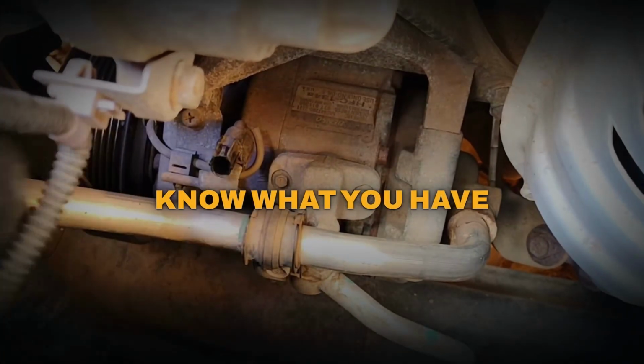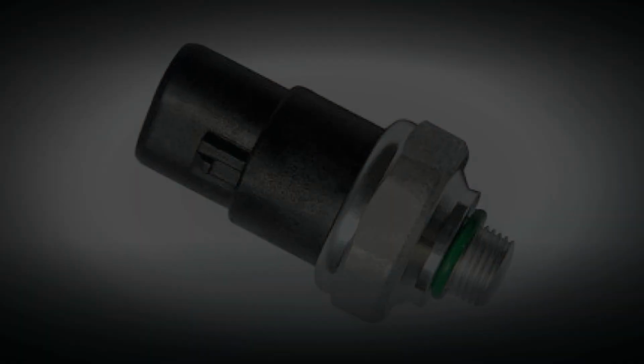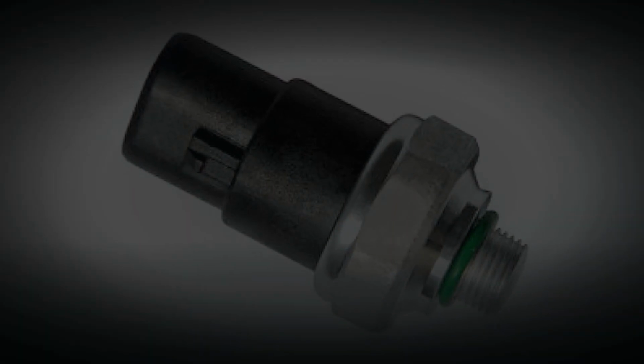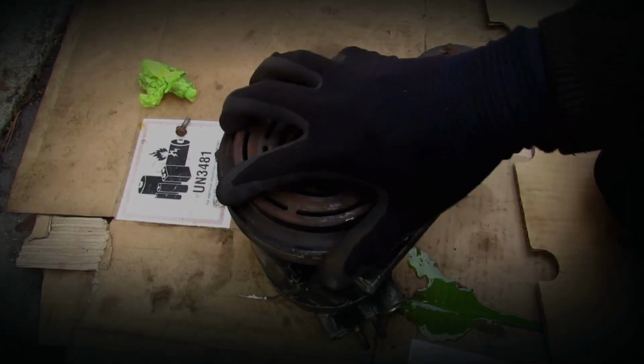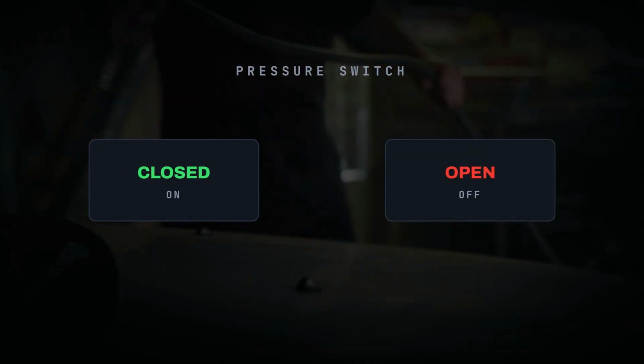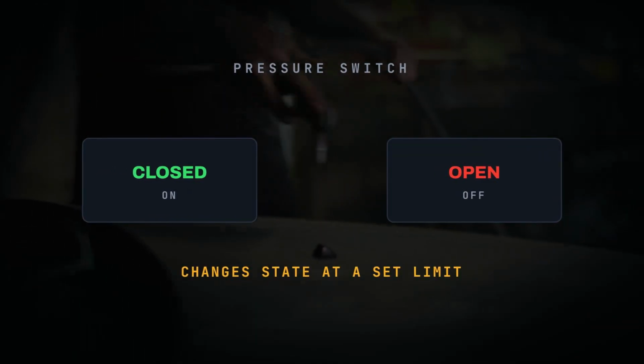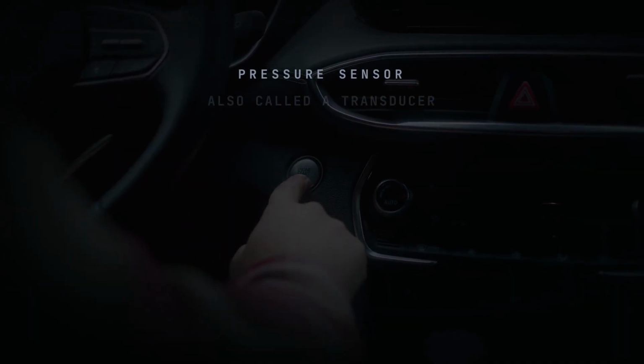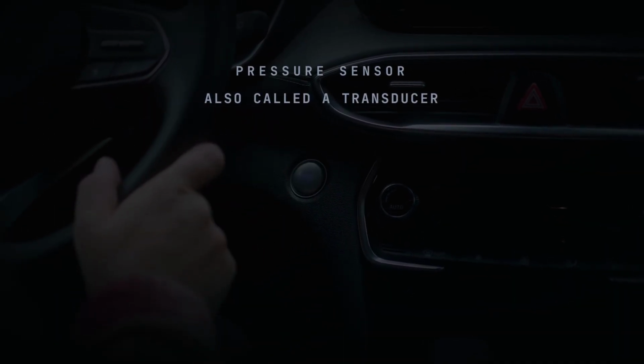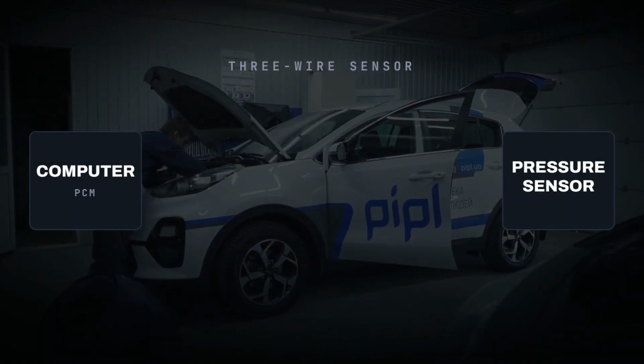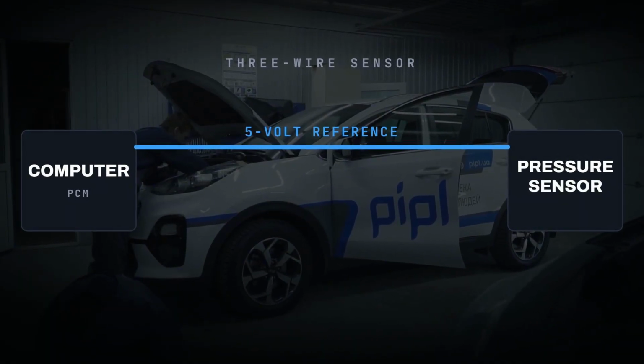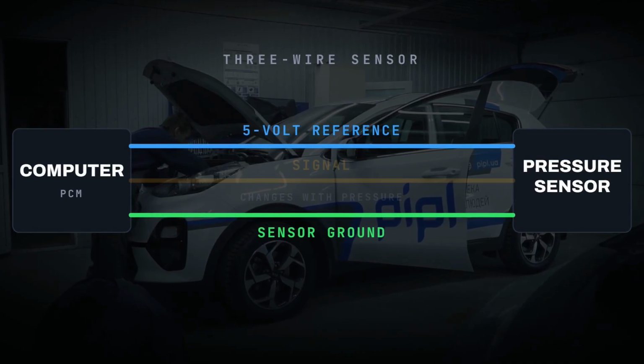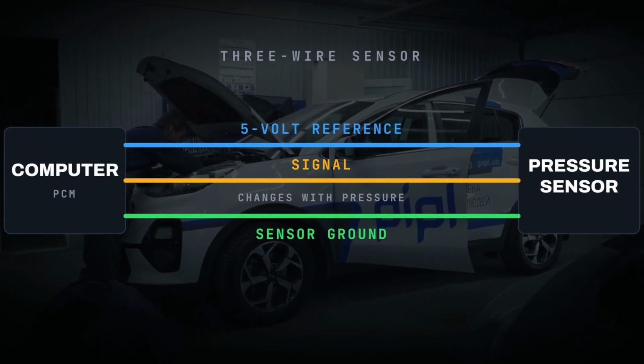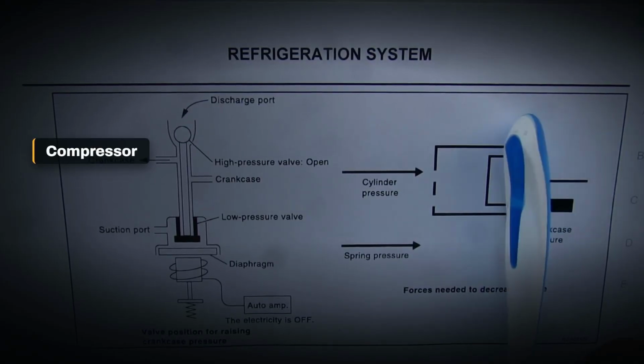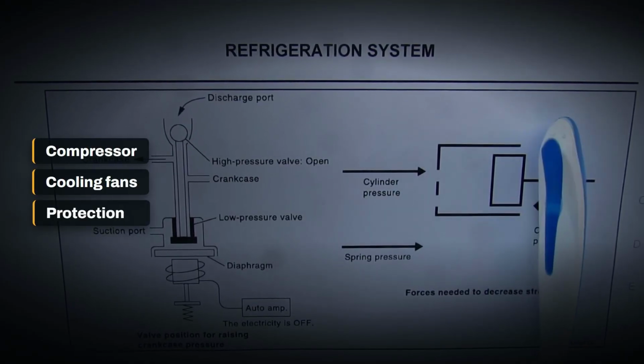Start by identifying what your vehicle actually uses. A pressure switch and a pressure sensor are often discussed as if they are the same part, but they may work differently. A traditional pressure switch is usually an on or off device. It changes electrical state when refrigerant pressure crosses a specific limit. A pressure sensor, sometimes called a pressure transducer, sends the vehicle computer a changing signal. A common 3-wire sensor receives a 5-volt reference and a sensor ground. The 3rd wire sends a signal that changes with refrigerant pressure. The computer may use that information to control compressor operation, cooling fans, and protection strategies.